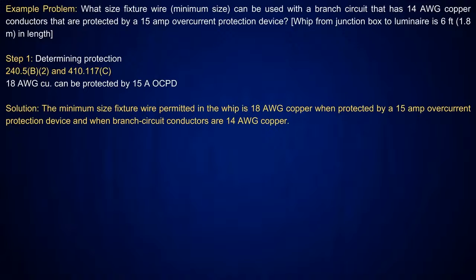Well, I've actually seen this before in the luminaires, where they say you cannot take that 18 gauge to a fixture, then go from fixture to fixture to fixture, because it has to tap directly to that junction box. I agree with that, because if you go from fixture to fixture and you put too many of them on there, then that wire size is not large enough. That would be a problem. I'm not necessarily calling it a tap, but I don't know personally the whole exact answer. From what I've seen, they're basically calling that a fixture tap to the branch circuit.